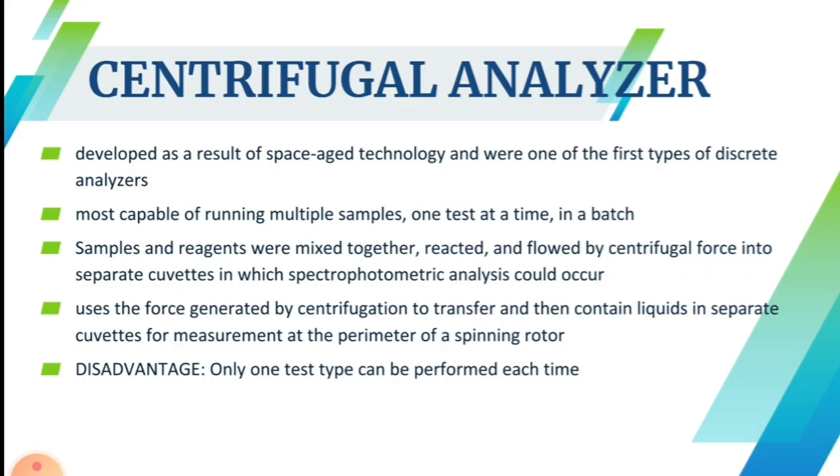Batch analysis is their major advantage because reactions in all cuvettes are read virtually simultaneously, taking no longer to run a full rotor of about 30 samples than it would take to run a few. Laboratories with a high workload of individual tests for routine batch analysis may use these instruments. Again, each cuvette must be uniformly matched to each other to maintain quality handling of each sample.